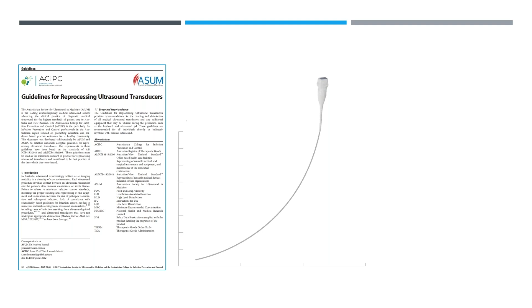So the core message of the 2017 guidelines is that ultrasound probes, I'm not talking about the machine, I'm specifically referring to probes, are classified as reusable medical devices in as much as they touch the patient. And because they are reusable medical devices, they need to be disinfected. They cannot be sterilized because that would denature the crystals and the ceramics that form the probes. They have to be disinfected.